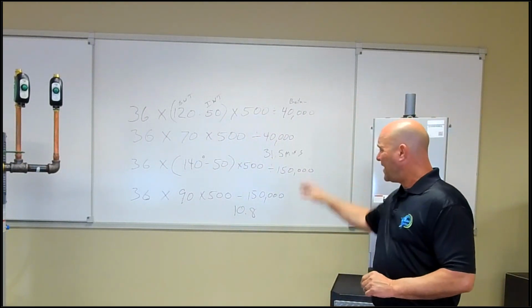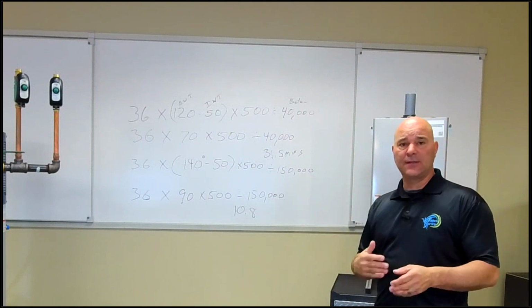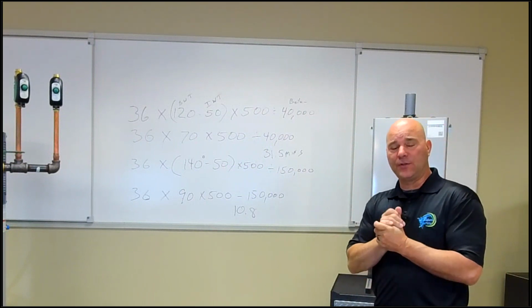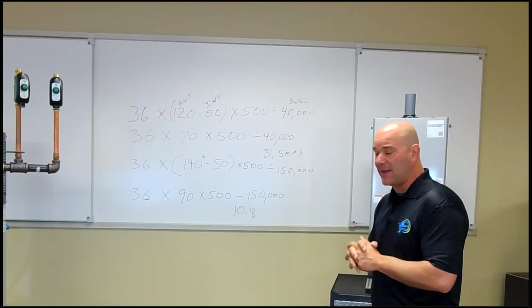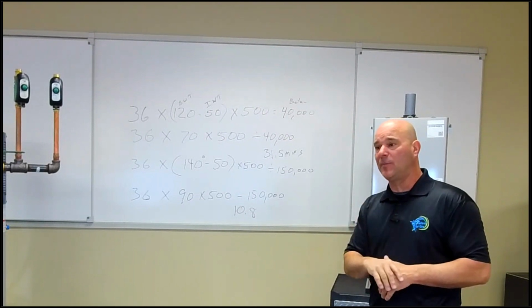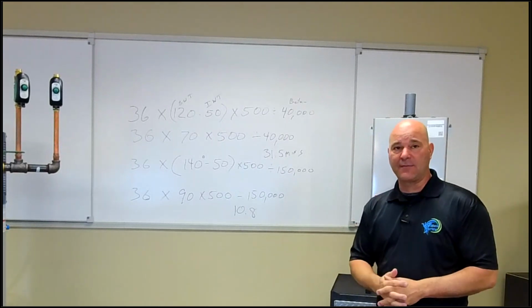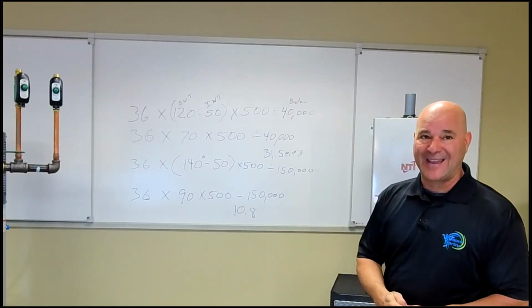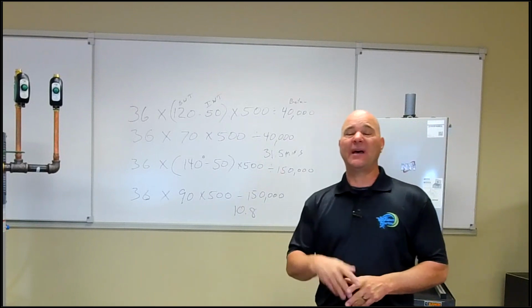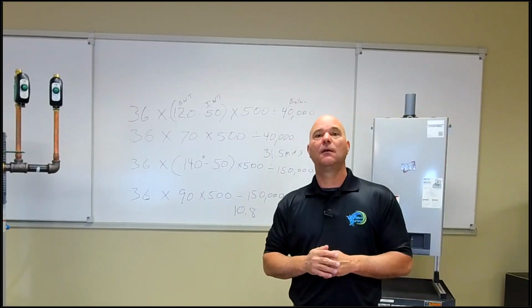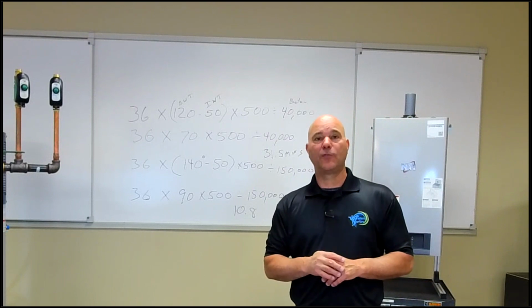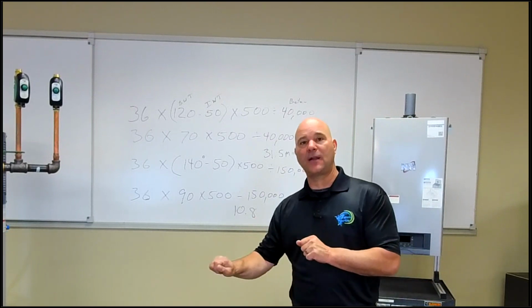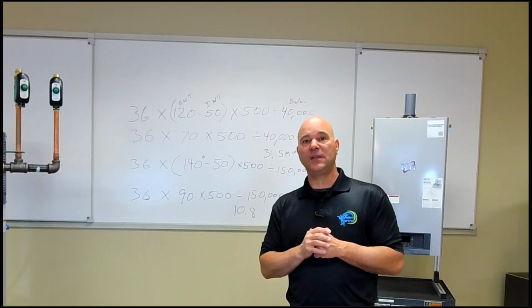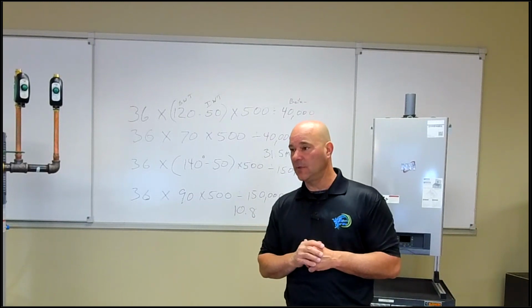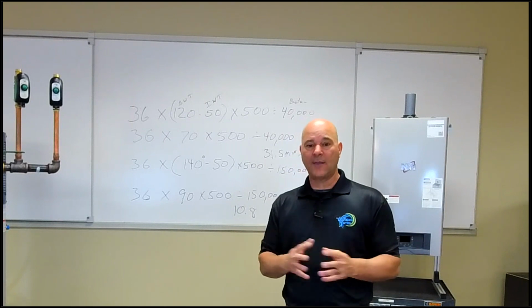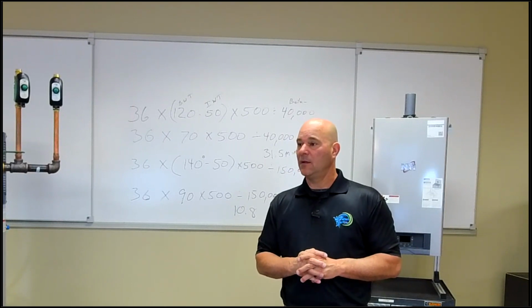So that is a recovery time chart. Hopefully this is another tool that you have in your toolbox. If you need it, it's there. Use it, take a snapshot. It will apply to almost everything. A 40,000 BTU tank style water heater. That was another reason that I used 40,000 BTU. If you have a 40-gallon standalone direct fired water heater with 40,000 BTU going in it, you can use the same calculation to figure out why they're running out of hot water. That was actually a question that just came in.